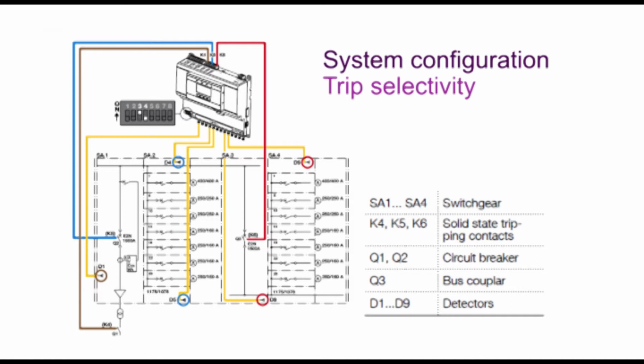In this instance, you have two boards with a bus coupler, so you're monitoring two sets of bus bars. Again, if detector 1 closest to the upstream breaker detects a light, and the current condition is anomalous, then the upstream breaker would trip. Detectors 3 and 4 would trip the second breaker after the upstream breaker. And the bus coupler breaker would trip if detectors 8 and 9 sense a light and you have the correct anomalous current conditions.